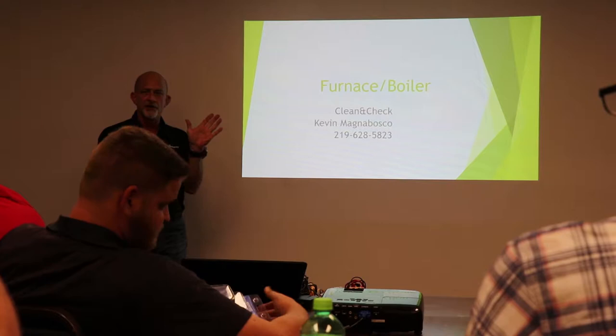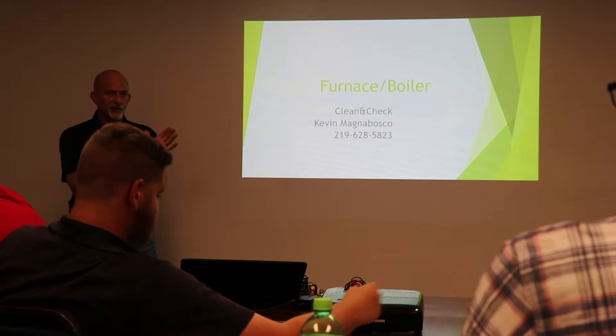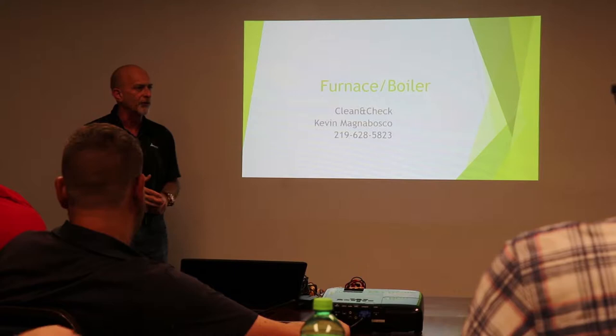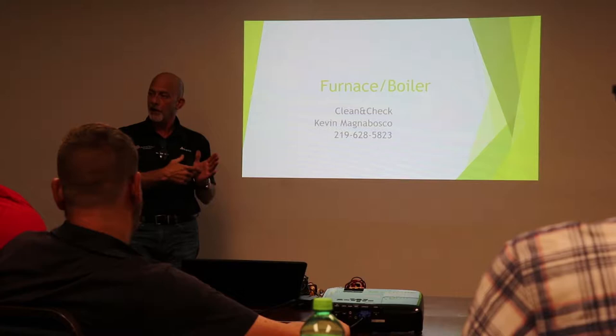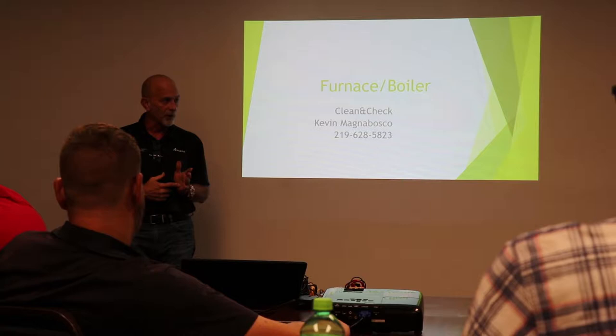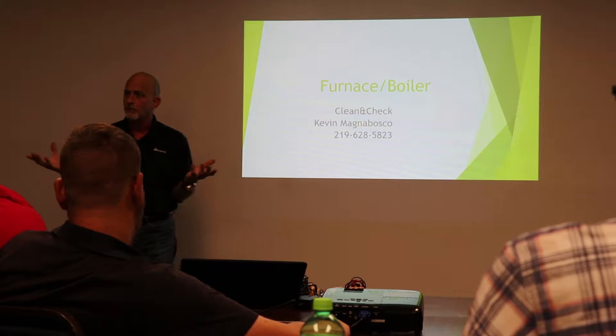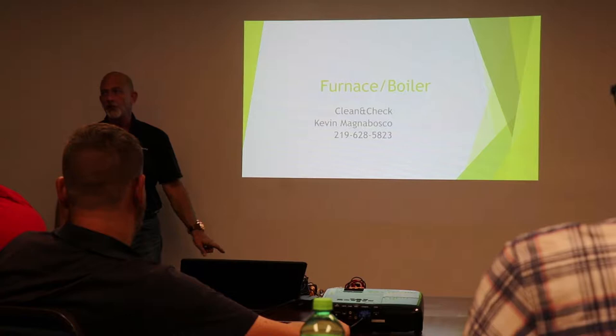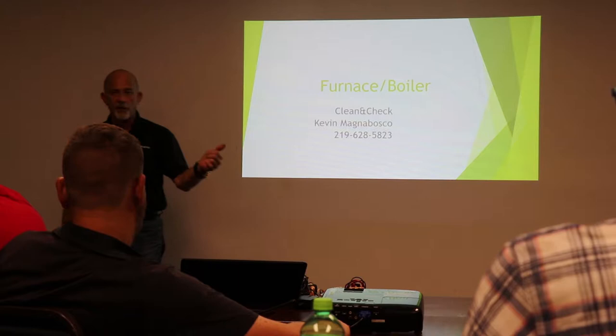So you can go out there, ohm out the compressor. If you're green, don't worry about it. Button the unit back up, now you can go in the house. If it's yellow, at that point in time, I'd call the customer outside and say, hey, checking out your system, I noticed that your compressor windings here are getting close to a fail point. Because that is actually measuring the lacquer coating on your windings to ground. It's measuring the resistance. If you're red, that compressor may have been running when they shut it off for the season, but most likely it's not going to start up in the spring. So now, remember, $39 cleaning check, right? We could potentially sell a brand new air conditioner.